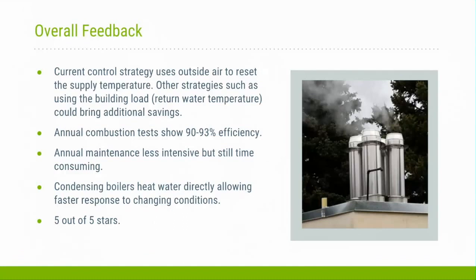Well, based on what Dylan was referring to, the higher return air temp that was coming back, we were doing outside air reset, and we had to have a controls contractor come back in and reprogram a different reset schedule for it. So right now here in Denver, at 20 degrees we're running 180 degrees, and at 69 degrees, we're running 130 degrees.